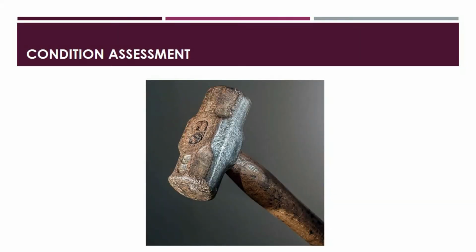Now, the assessment process begins with a simple visual evaluation of the wood poles, followed by basic physical testing such as poking test for surface condition and hammer test for internal decay indications. Many utilities use this method largely as a safety process for linemen to follow before climbing.